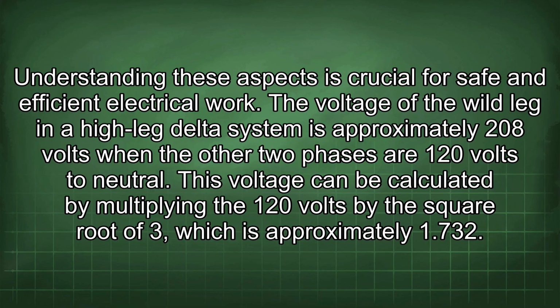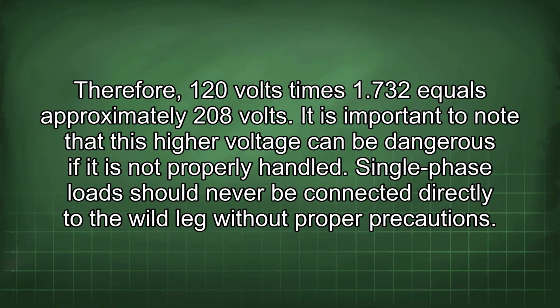The voltage of the wild leg in a high-leg delta system is approximately 208 volts when the other two phases are 120 volts to neutral. This voltage can be calculated by multiplying the 120 volts by the square root of 3, which is approximately 1.732. Therefore, 120 volts times 1.732 equals approximately 208 volts.